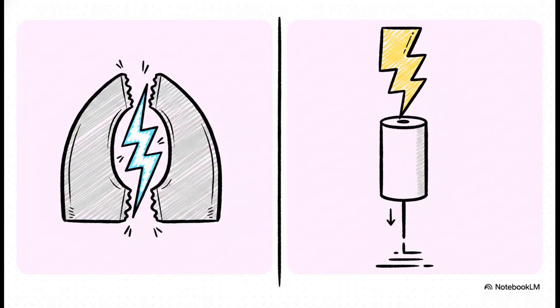Now, what's really interesting here is how we handle massive overvoltage, like a direct lightning strike. On one hand, you've got arcing horns. These are deliberately designed as a weak link in the system. They're essentially just two metal points positioned so that if a surge overwhelms the insulation, the arc jumps between these horns in the open air, rather than punching through the bushing or the winding insulation. They're cheap, they're sacrificial open-air spark gaps, and honestly, they save a $50,000 unit from a catastrophic bushing failure.